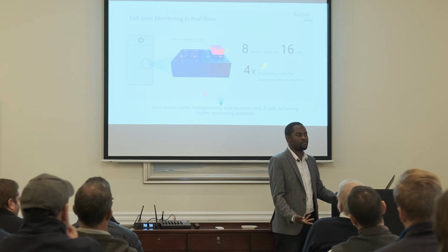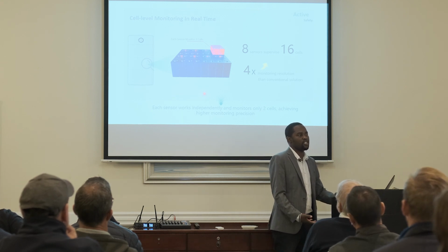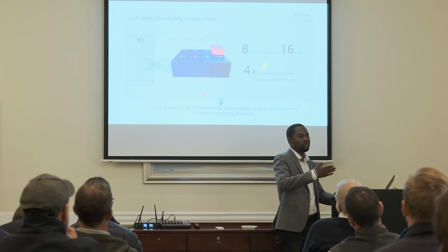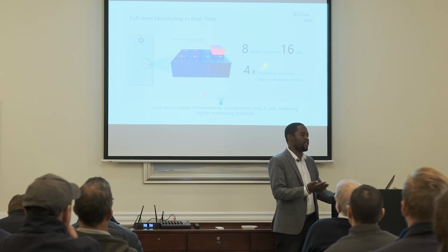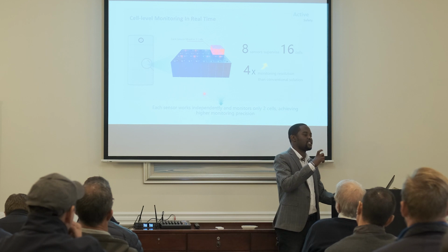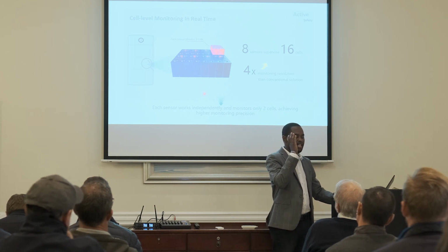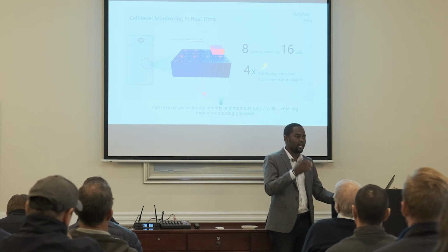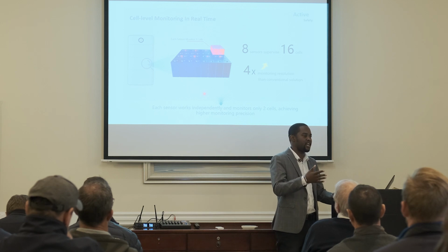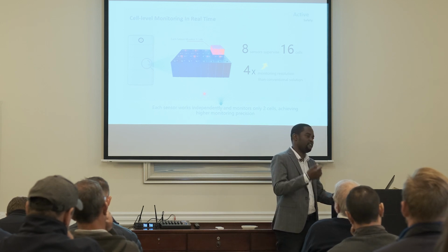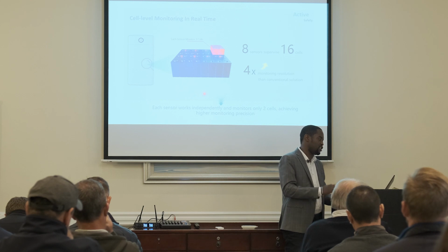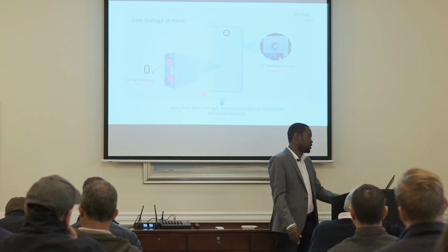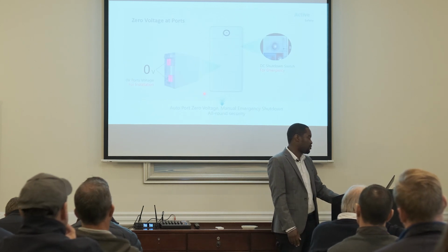If you look at the systems out there, you don't get that technology. The best that we have will be one sensor supervising 4 modules. But Huawei made it so that one sensor is supervising only 2 modules, taking information about the charge current, the discharging, the temperature, if there's any fault, and if the voltage is still within range. So all those systems, you get them. So there's another protection mechanism.